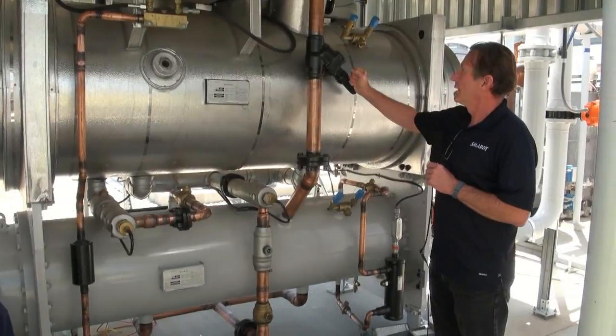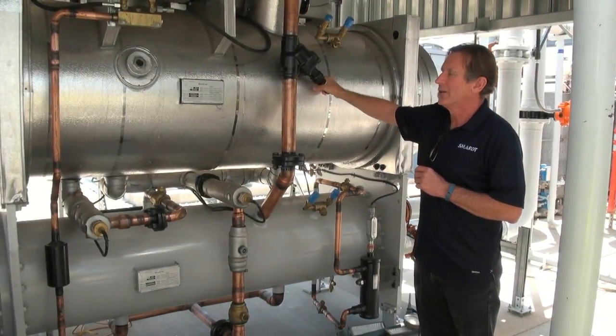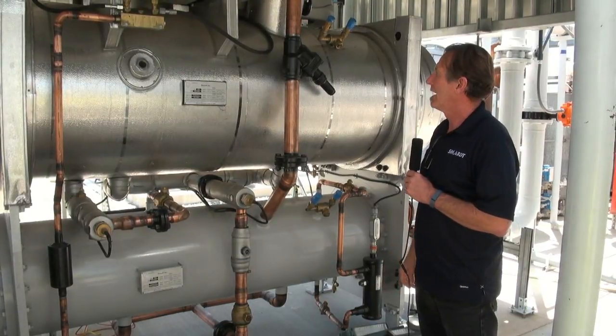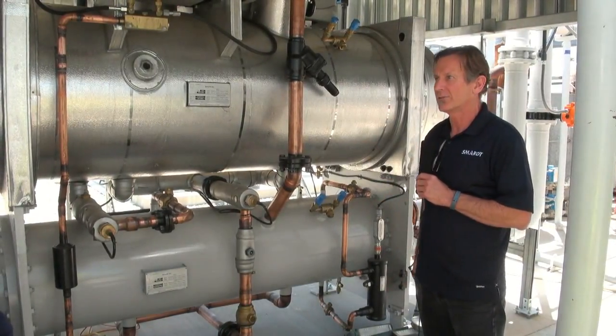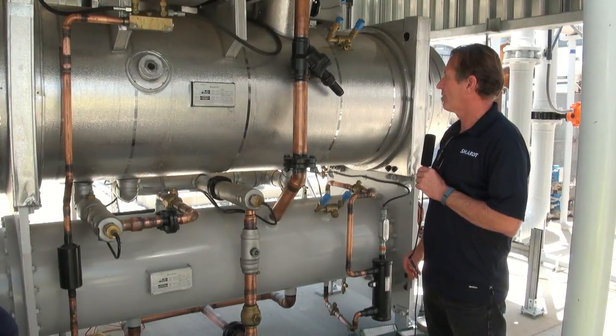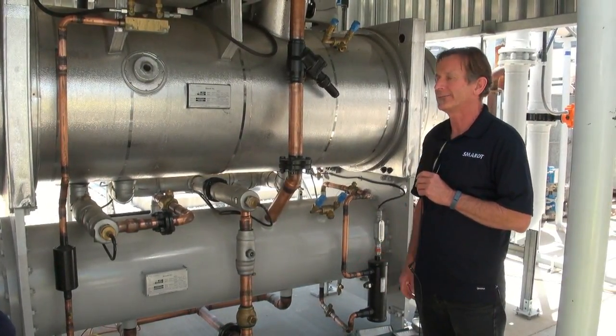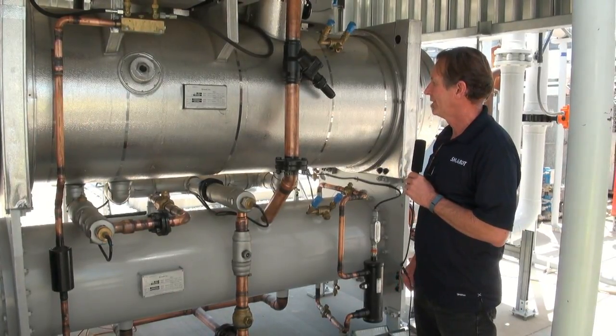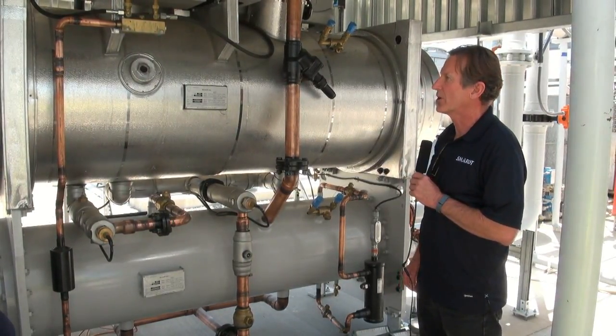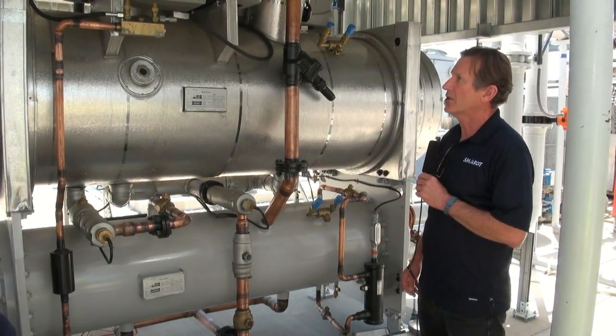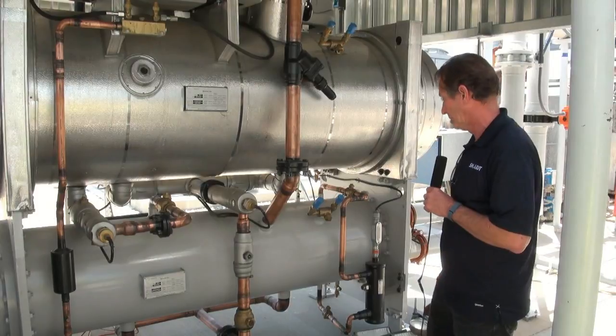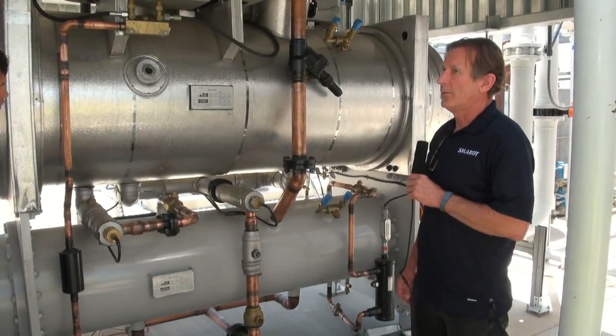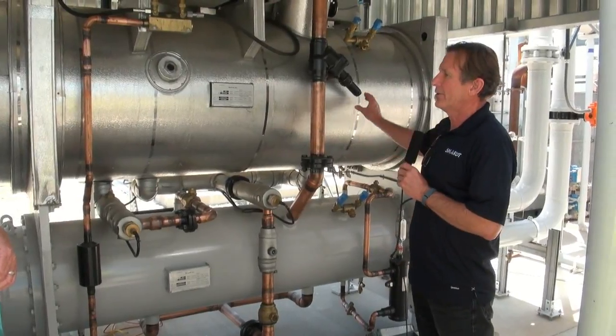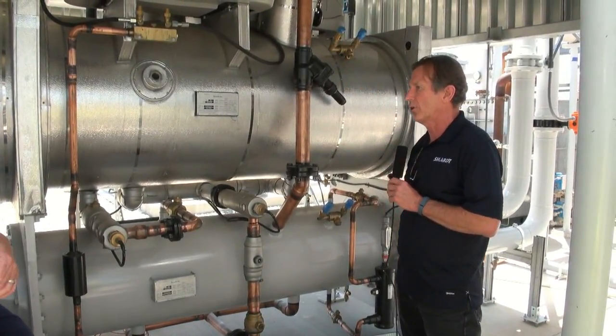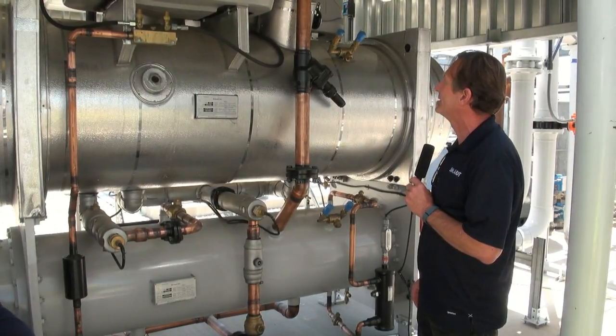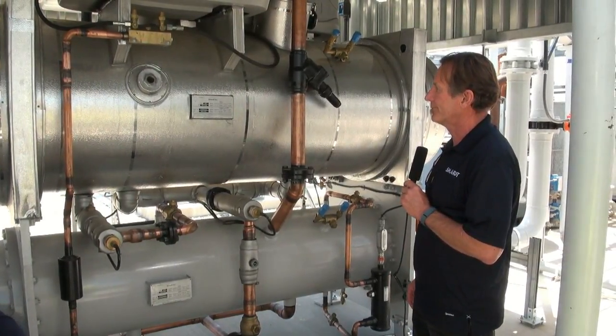This is the check valve that you hear chattering on occasion. It's cast iron, very robust. It's a piston type, so it has very, very few issues. Even though they chatter, don't be alarmed. It's kind of normal operation. You'll hear them chatter, especially on startup, especially on sequencing between each compressor. Yeah, it's double duty. You can use it as an isolation valve. It has a stem on it that you can close that secures the refrigerant on the high side if you needed to open the compressor.